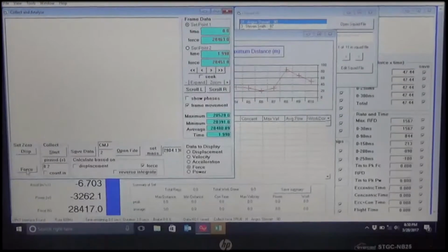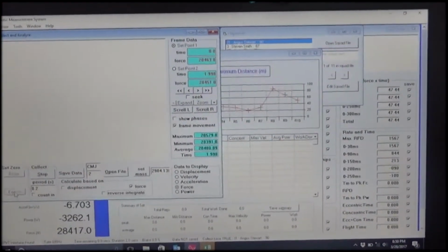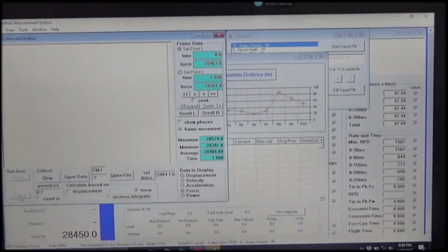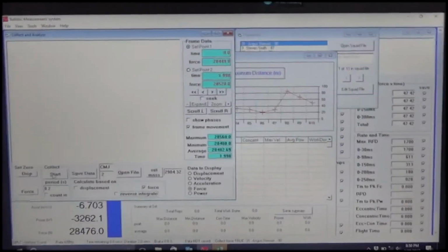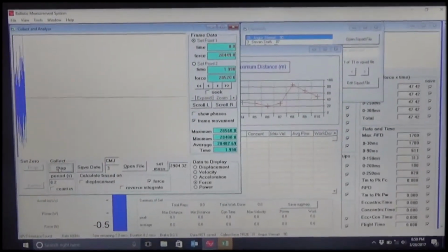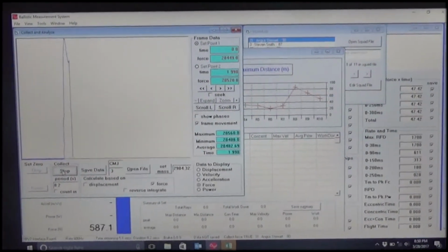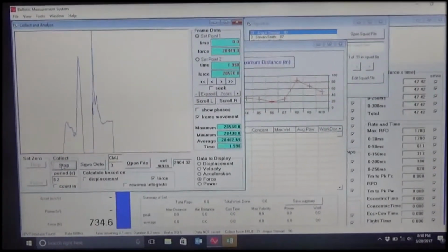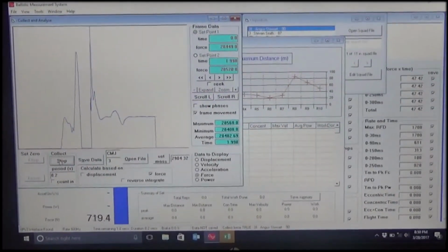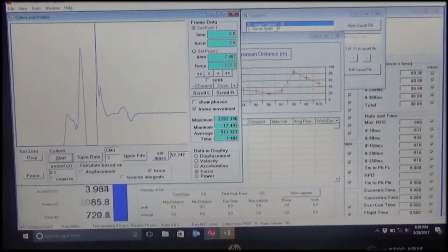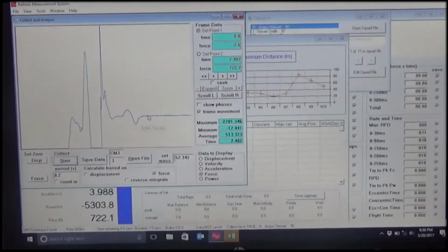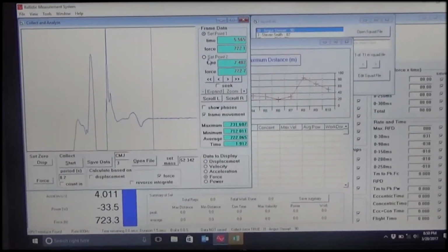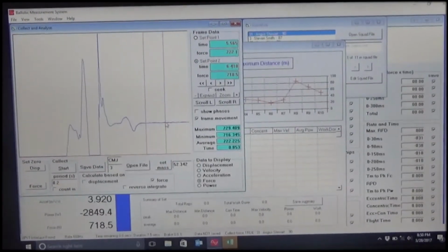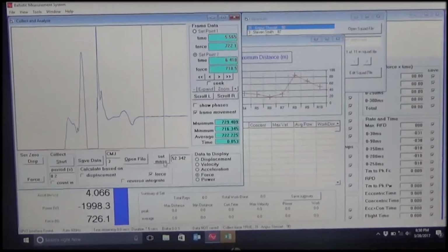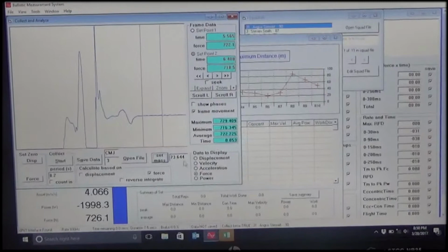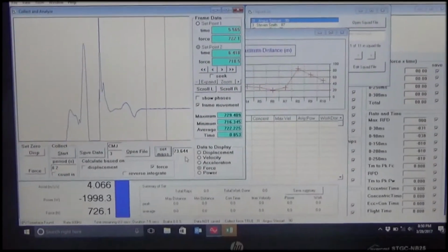To assess the accuracy of the calibration, we've set 0 for force. We ask the athlete to jump on the force plate and do a little jump and hold. 1, 2. We stop there. We get the set point 1 through here and the set point 2 we set here. Set mass: 73.644. The force plate is accurate.